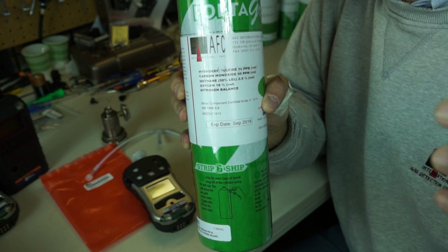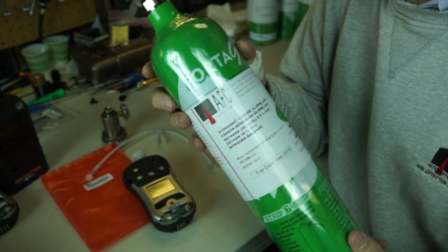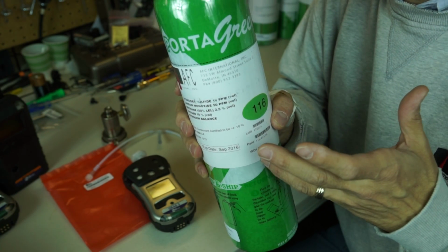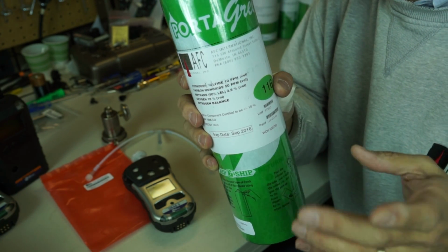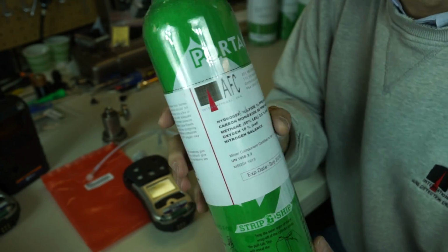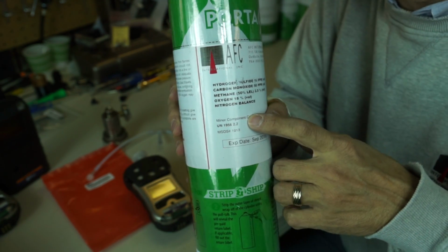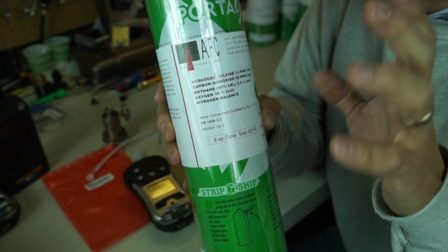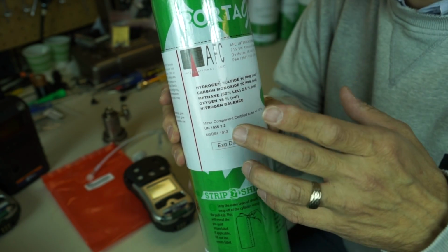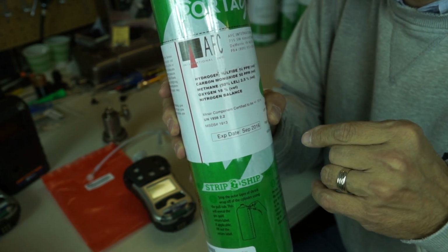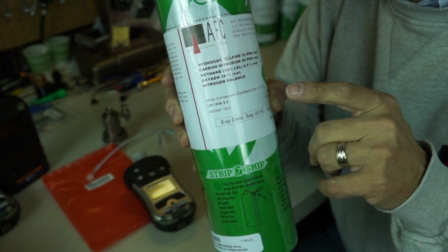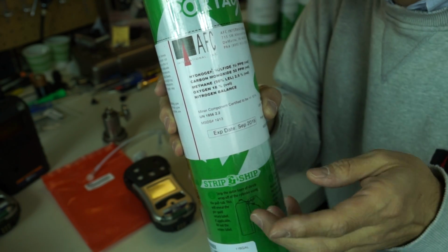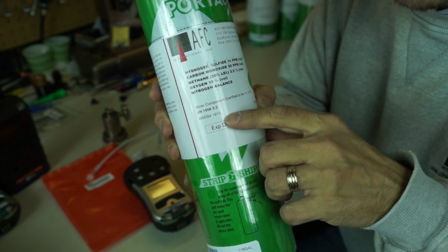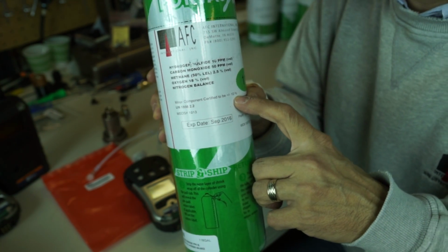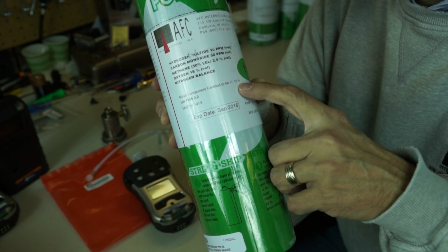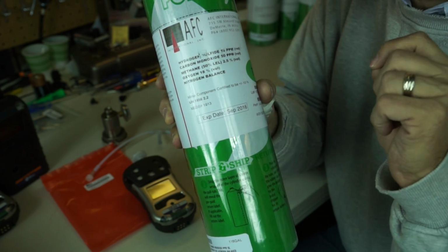But as far as gas goes, this happens to be a cylinder from Portagas. They are a third-party vendor for gas, very, very good quality gas. You've heard me talk about them on other videos, and this is their Porta Green cylinder. But you will see that it doesn't really matter. Gas is gas, and the most important thing you need to understand is as long as they give you a certificate of accuracy and precision, then that gas is good. And there should be an accuracy statement, and in this case, the Portagas company has put the accuracy and precision statement right here, plus or minus 10%.